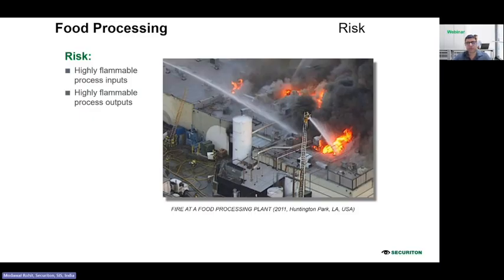If you talk about the implications, then early detection is critical. The reason is obvious, because fires spread rapidly due to the flammable substances. So special fire detection is recommended in areas like mixing areas where your input is at risk. Then you have drying, baking, and frying lines, which are basically ignition sources. And of course, at the storage and packaging zones, you can go with a heat detection system or even early warning smoke detection as well.